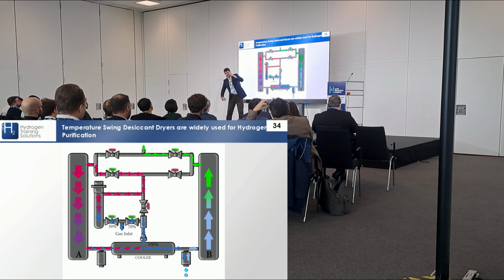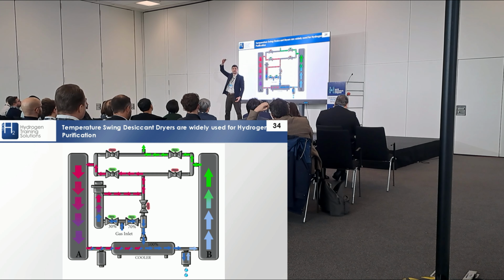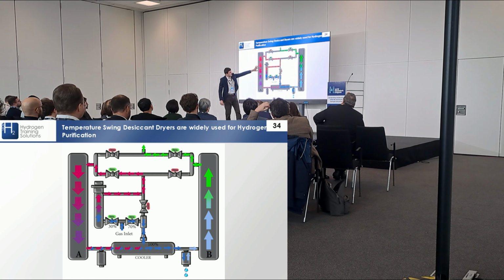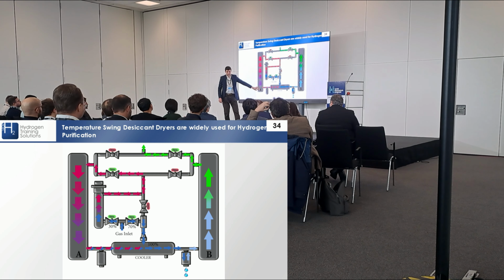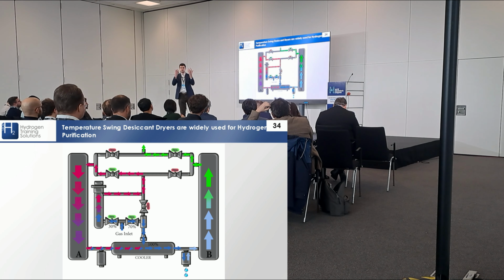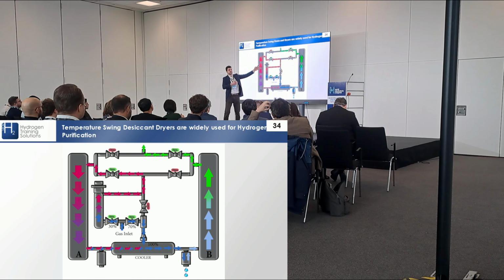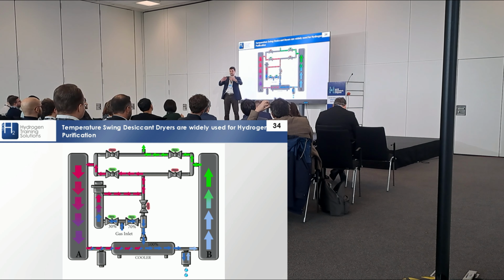You've just lowered the relative humidity because you've heated up the gas. You pass that really hot gas through column A, and the way you can think of the desiccant is: if you pass hot gas, it will release the moisture, and if you pass cold gas through it, the desiccant will suck in the moisture.